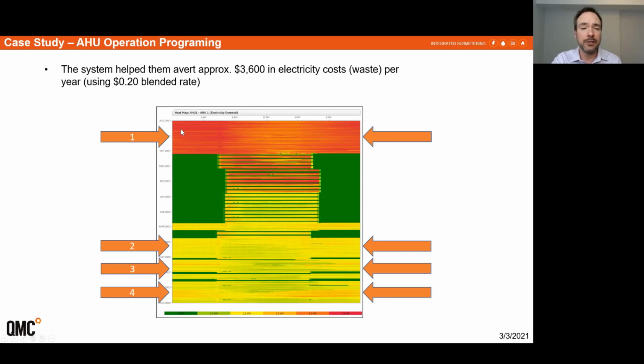This is a LEED project, and when the air handling unit this meter was monitoring was installed, in the summer months it was actually operating 24/7. In this heat map, red indicates a very high energy intensity, so for every day it was operating midnight to midnight at a very high rate, shown in deep red here.